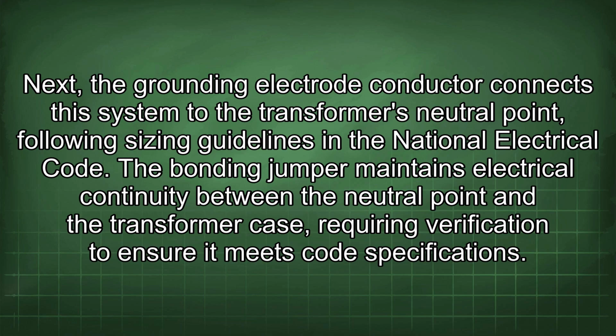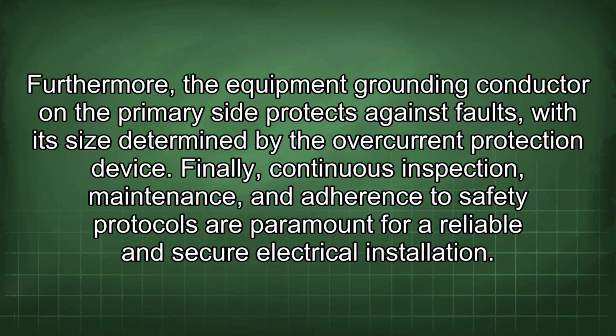Next, the grounding electrode conductor connects the system to the transformer's neutral point, following sizing guidelines in the National Electrical Code. The bonding jumper maintains electrical continuity between the neutral point and the transformer case, requiring verification to ensure it meets code specifications. Furthermore, the equipment grounding conductor on the primary side protects against faults, with its size determined by the overcurrent protection device.